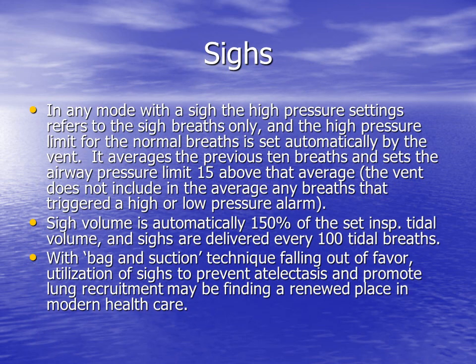It should be mentioned that if you choose to utilize the Sigh function, this high pressure limit you will set on the vent will then refer to the Sigh breaths and not the set breaths per minute. Instead, the vent will average the PIP of 10 breaths and then auto-set its own internal high pressure limit, 15 above that average. Sigh volume is not a directly set parameter. Rather, it will be 150% of the set inspiratory tidal volume, and the patient should receive a Sigh breath about every 100 breaths.